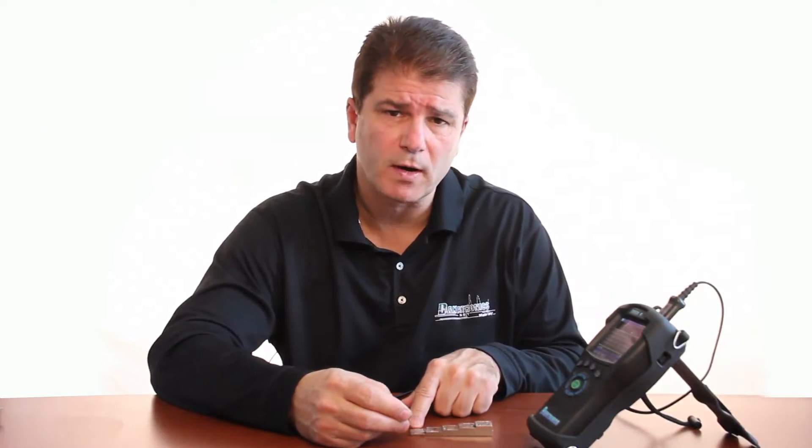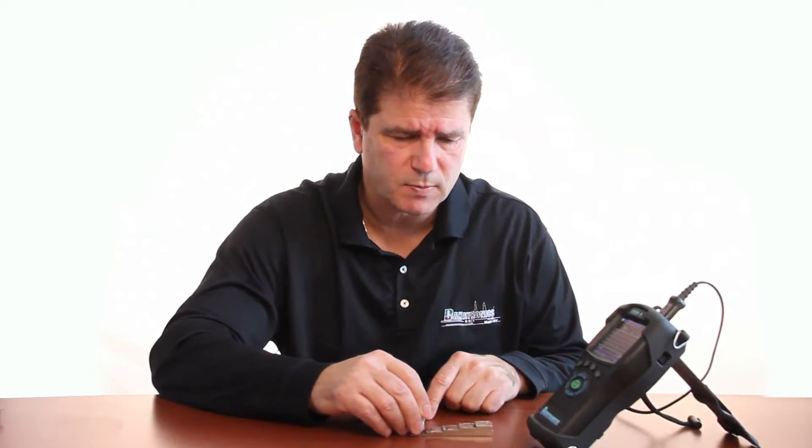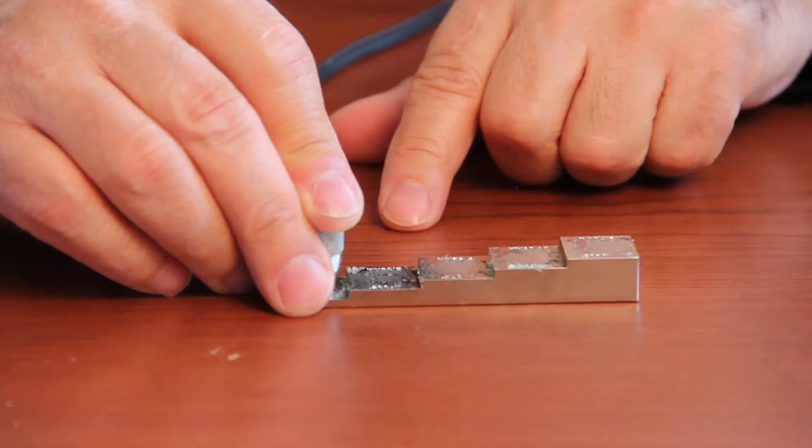I have a five-step test block from one hundred thousandths to five hundred thousandths of an inch. I add some couplant to the test block and press firmly on the disc.